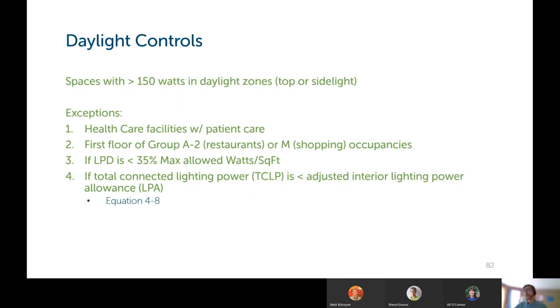Daylight controls: spaces with more than 150 watts within a daylight zone, whether that's from a window or a skylight, need to have daylight controls. Exceptions to that are healthcare facilities where there's patient care occurring, and the first floor of occupancy group A2 buildings, which is restaurants, or group M, mercantile shopping buildings. They do not need to have daylight controls. If the LPD, the lighting power density, is less than 35% of the maximum allowable watts per square foot, you don't need daylight controls.